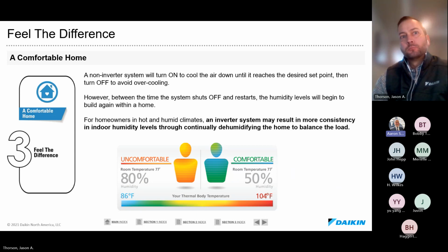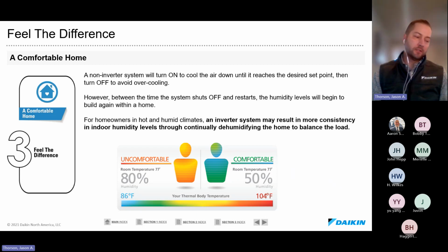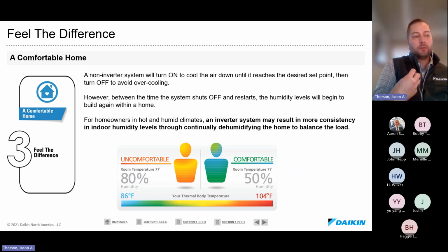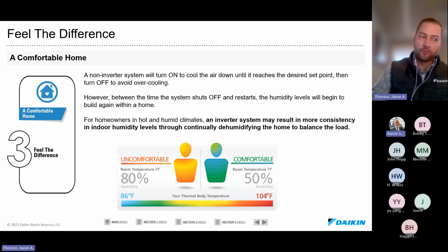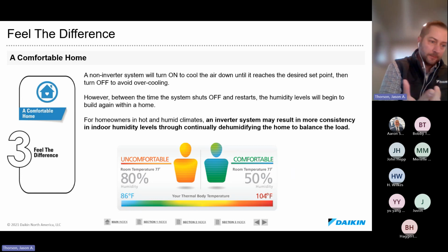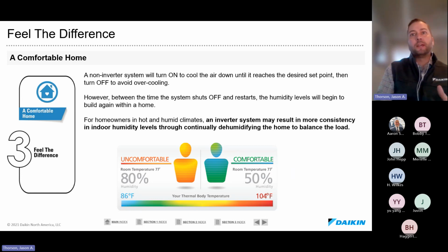So when you have that on-off cycling, you're not getting air across that coil, you're chasing the temperature. And that's the thing: even if it's 72 degrees and you don't need that full cooling capacity, it's still pulling air over the coil, through the filter box, and back into the space for cleaner air and removing humidity, even when it doesn't need to crank down to some ice cold temperature. So the beauty of an inverter is it's never really on-off. It just ramps up and down gently as needed.